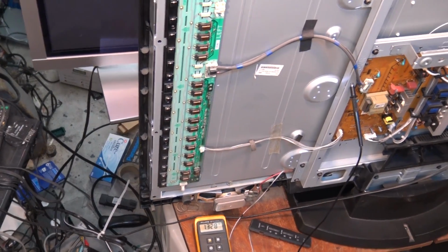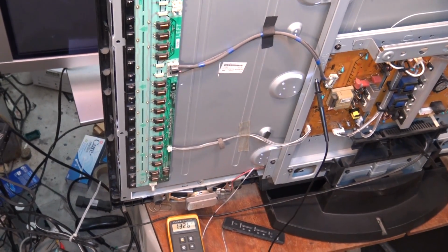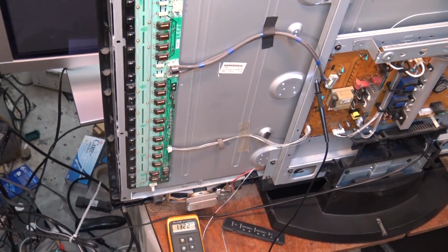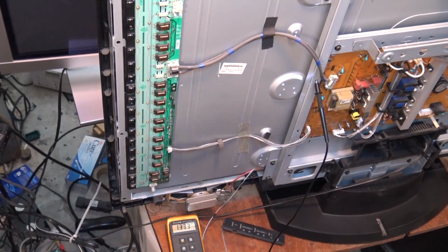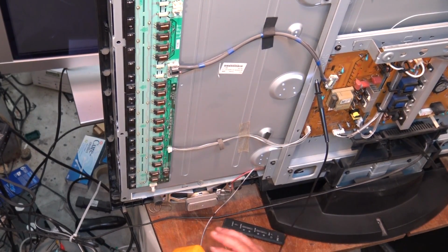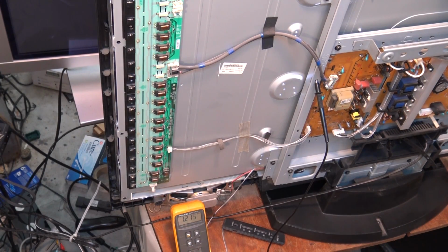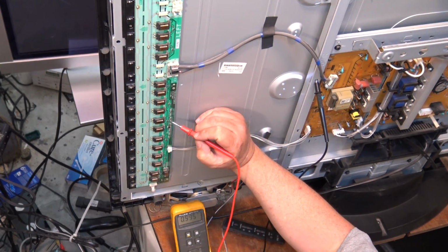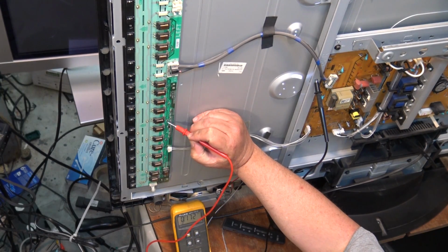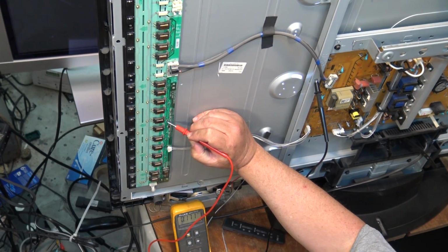What you're looking for is consistent voltages between each of the transformers, or each side of the diode - it's a dual diode. You put your meter in the AC voltage test mode, and you'll measure each side.